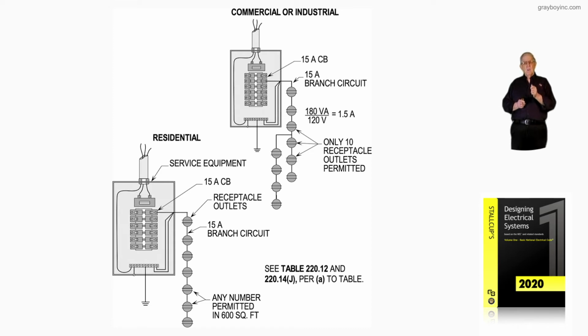And they may have an ordinance that says, no, on a 15 amp circuit, you can place 8 outlets. On a 20 amp circuit, number 12 wire, you could place 10. We're limiting the number. But if they go right by the code, there is not any particular number in that square footage area as long as you don't trip the overcurrent device in the panel board.